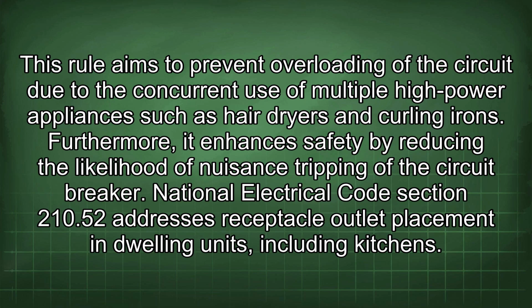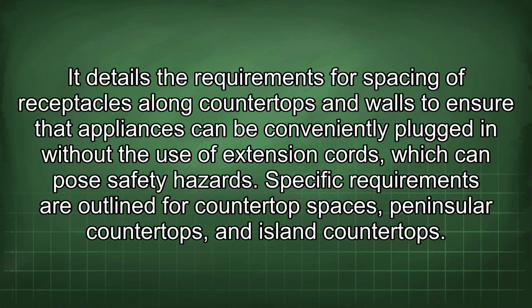National Electrical Code Section 210.52 addresses receptacle outlet placement in dwelling units, including kitchens. It details the requirements for spacing of receptacles along countertops and walls to ensure that appliances can be conveniently plugged in without the use of extension cords, which can pose safety hazards. Specific requirements are outlined for countertop spaces, peninsula countertops, and island countertops.